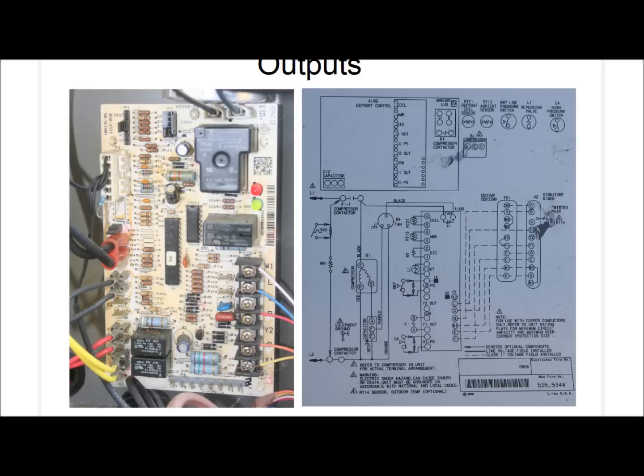All right, so here we're going to talk about outputs. Now let's go back to our control wiring and our terminal block. We didn't talk about the W terminal, and that's because that is a control voltage output. When this heat pump goes into the defrost mode, what it does is goes back basically into the cooling mode. So when you're heating and it frosts up and it needs to defrost, it goes back into the cooling mode. Well, that's not very convenient or comfortable for someone in the home.